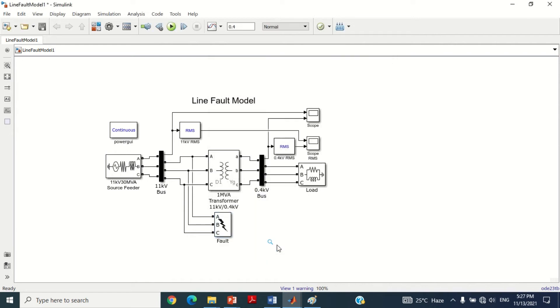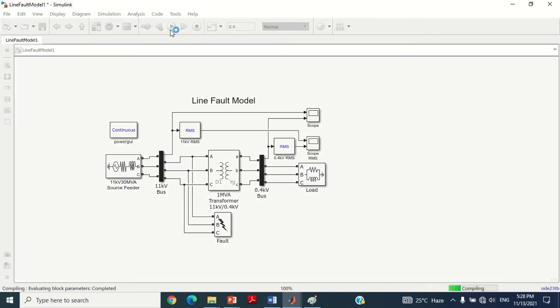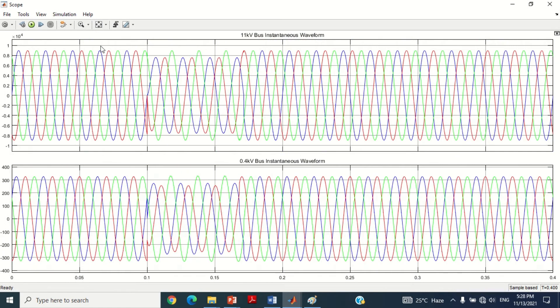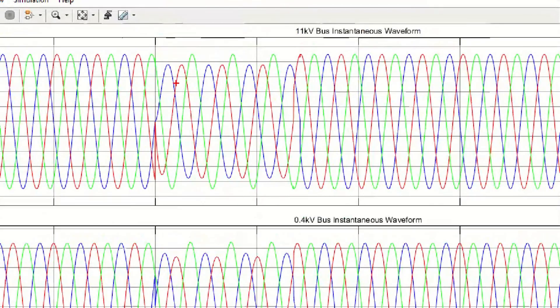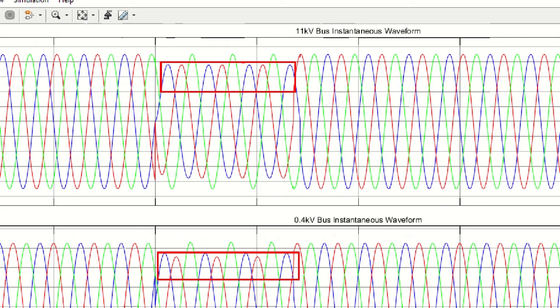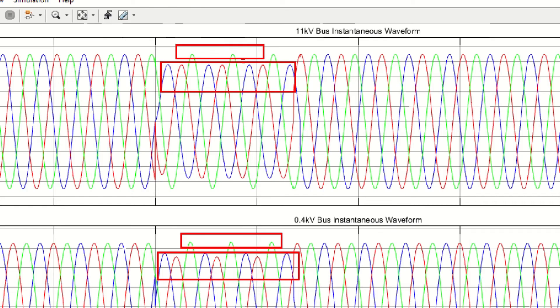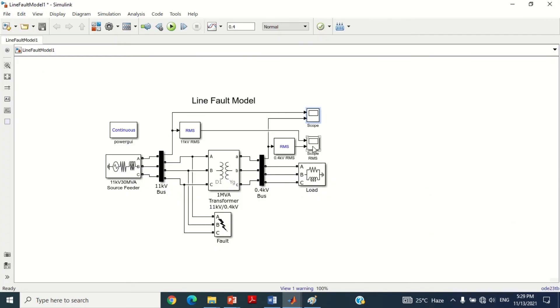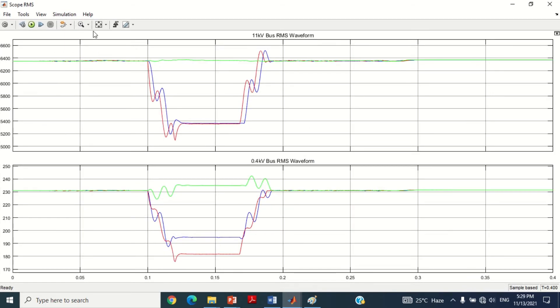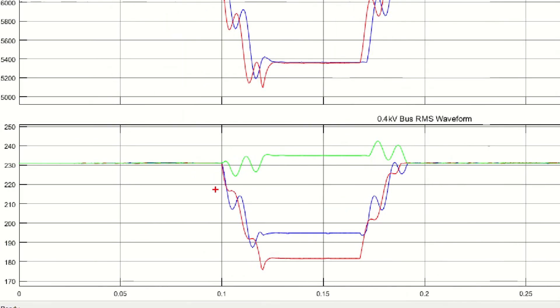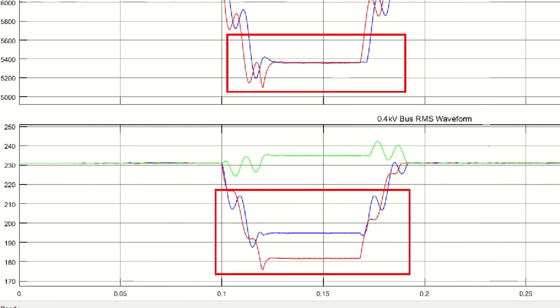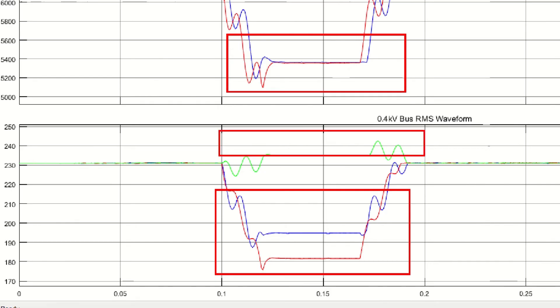Friends, at this stage we have fully discussed every block of the model. Now let's run the simulation by clicking on this play button. Double-click on this scope to check the instantaneous voltage graph both at the sending end and receiving end side. You can see when double line to ground fault is applied at phase A and phase B, the voltage of both phases A and B decreases resulting in voltage sag. On the other hand, the voltage of phase C increases resulting in voltage swell. Now double-click on this scope to check the RMS voltage graph. You can see voltage sag occurred in phase A and phase B, whereas voltage swell occurred in phase C at the receiving end side.